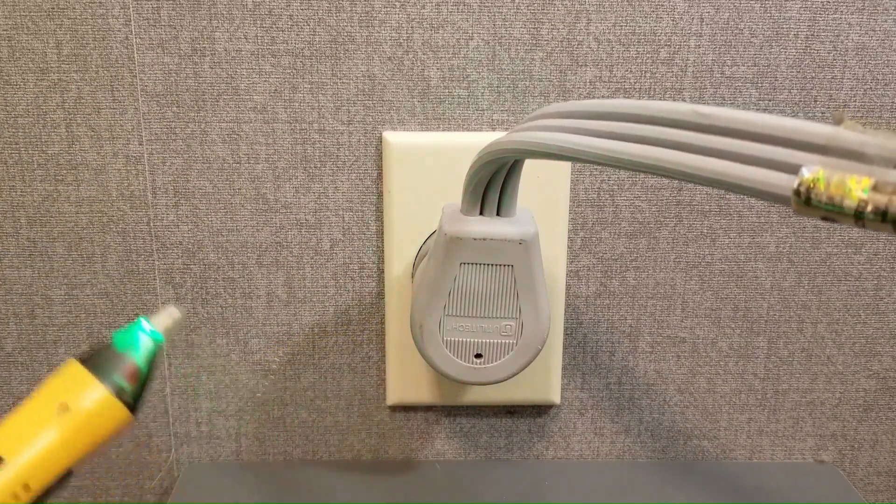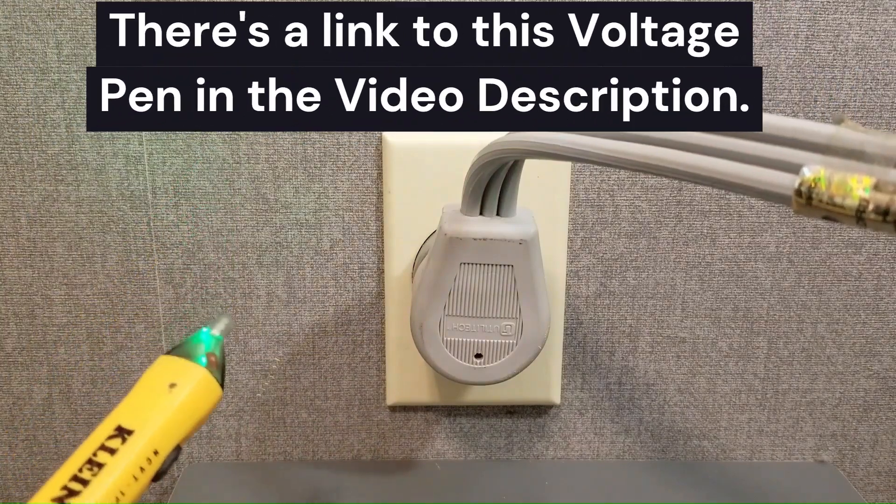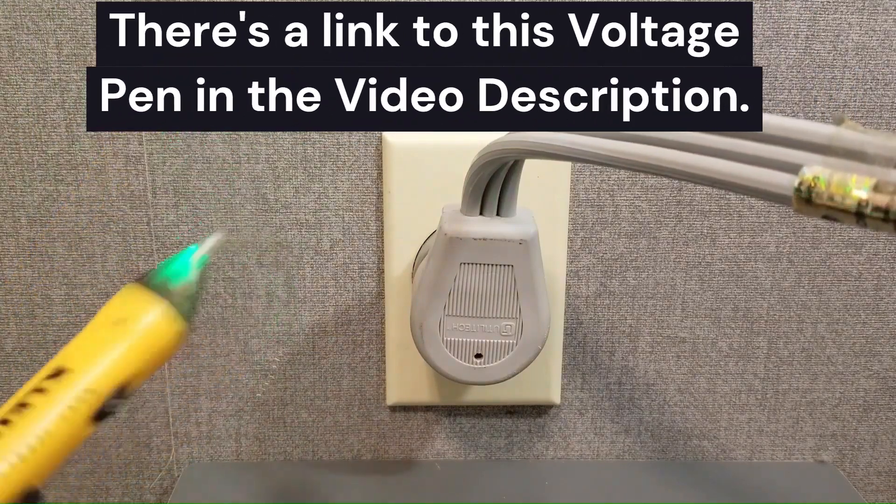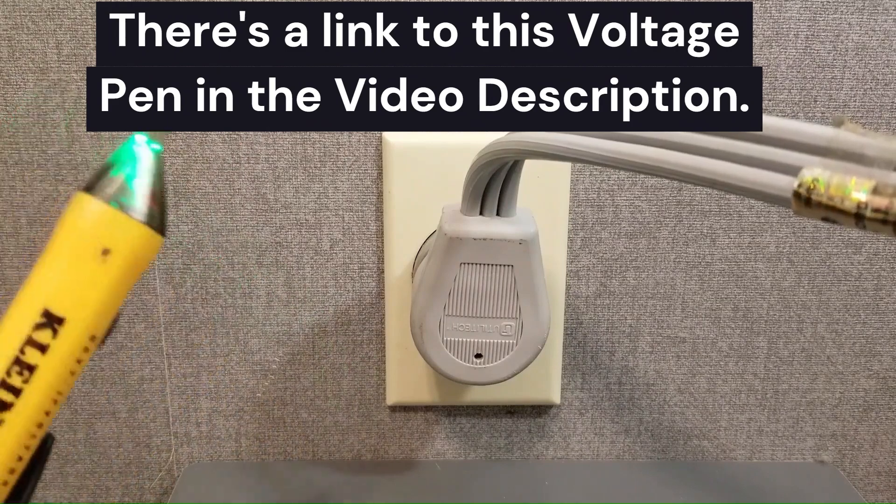Okay that is neutral. Neutral should not do that. Neutral shouldn't signal at all. It should be at ground potential. So this is one way that you can tell if you have a floating neutral.